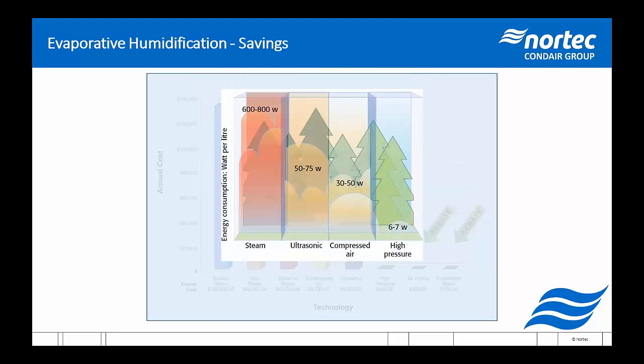To simplify it a little bit, for steam you're looking at 600 to 800 watts per liter. We've gone metric here. 50 to 75 watts per liter for ultrasonic, 30 to 50 watts for compressed air, and 6 to 7 watts for high pressure. And that high pressure can go back to the DL or the evaporative media as well in terms of energy usage.